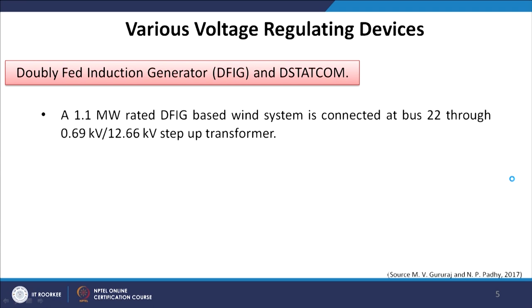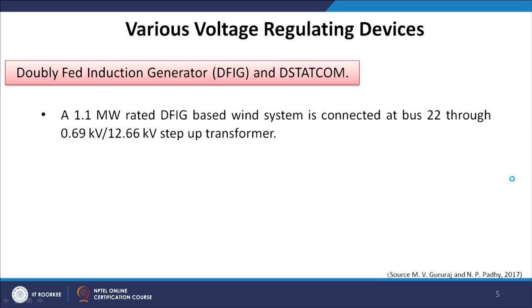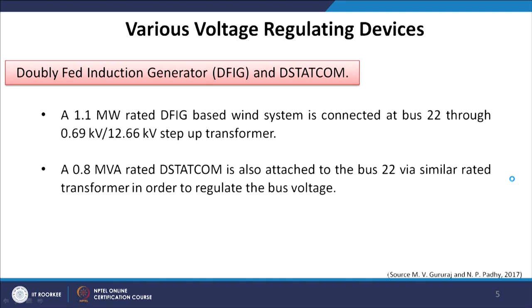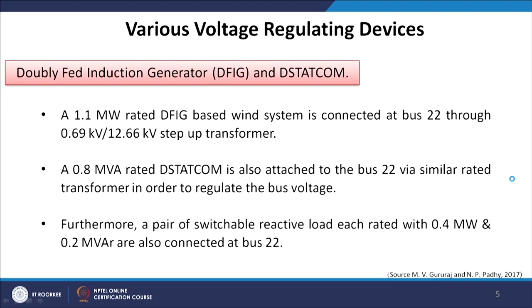Similarly, the DFIG and DSTATCOM are additional devices placed to take care of the system reactive power scenario. A 1.1 MW rated DFIG-based wind system is connected at bus number 22 through a 0.69 kV / 12.66 kV step-up transformer. A 0.8 MVA DSTATCOM is also attached at the same bus. Furthermore, a pair of switchable reactive loads, each rated at 0.4 MW and 0.2 MVAr, are also connected at bus number 22.